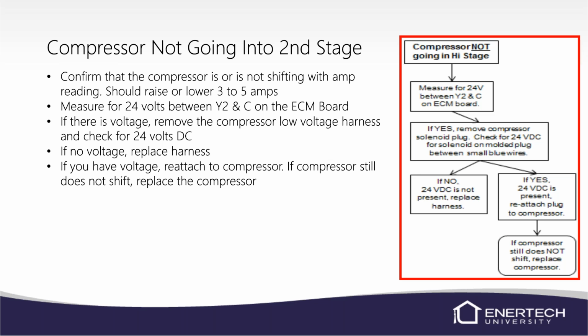If you have voltage, you can reattach it to the compressor. If the compressor still does not shift, you'll have to replace the compressor. There's no replacing the second stage solenoid. It's internally in the compressor, so you'll have to replace the compressor on that.